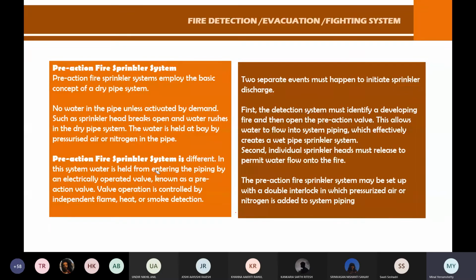For this action to begin, you need two separate events, and both must happen to initiate sprinkler discharge. Otherwise the sprinkler won't discharge, and in case of a mistake, your property can be saved. In case of an actual fire, two actions will happen anyway, because someone will take action and you'll be saved. But in case of a mistake, you'll get some time to save your stuff.